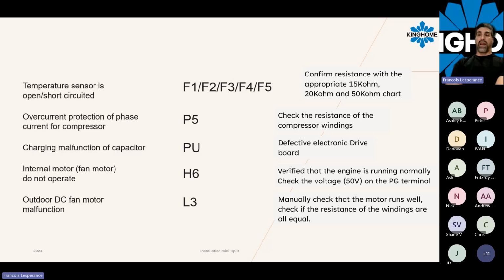H6 is related to the fan motor, the indoor fan motor. There is some troubleshooting that you can do for that. We can check if we have 50 volts on the PG terminal directly on the board, which is the feedback from the motor. If we have the feedback from the motor and the motor is not running, or you still have this H6 error, well, that means the fan motor is defective. If we don't have the voltage, that means the indoor board is defective. You can just turn the wheel of the motor, make sure the shaft is okay, and then order the new board.